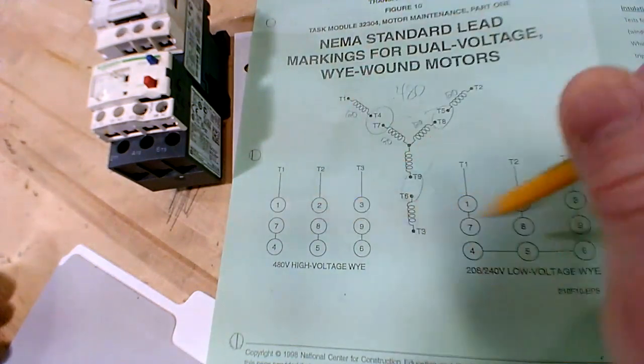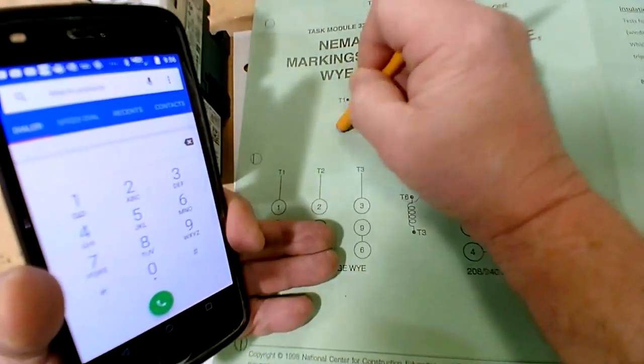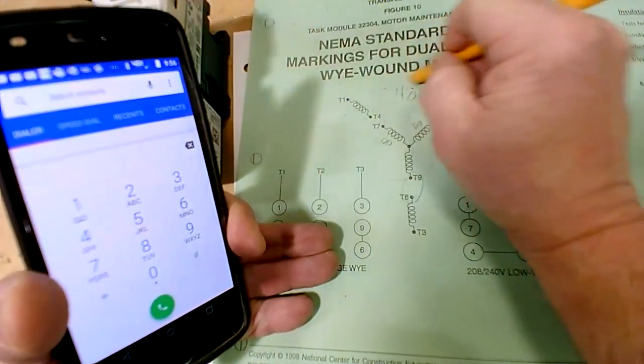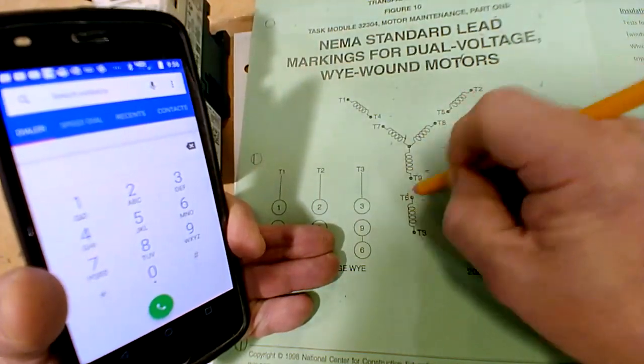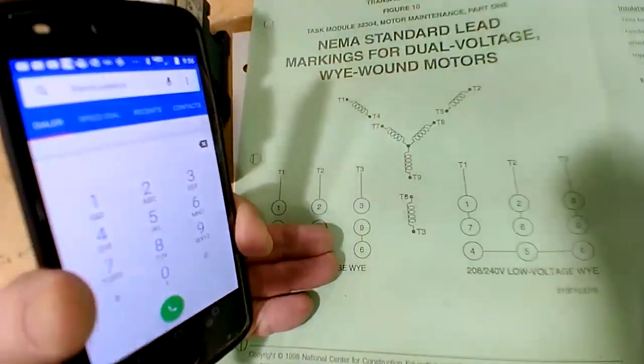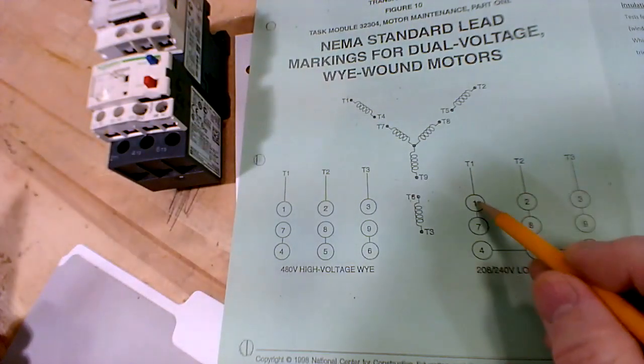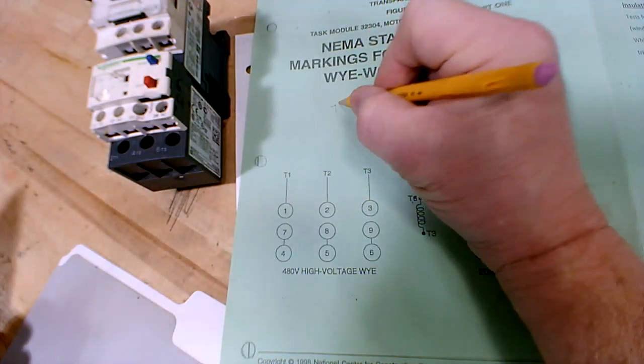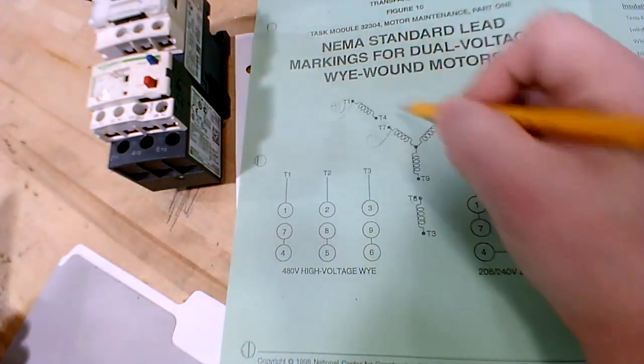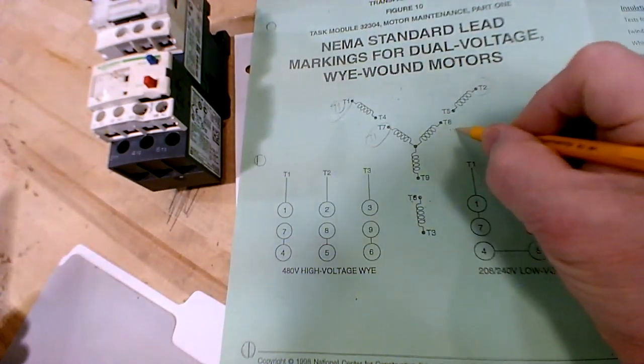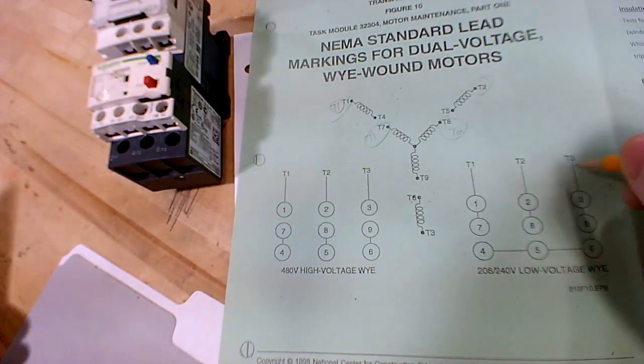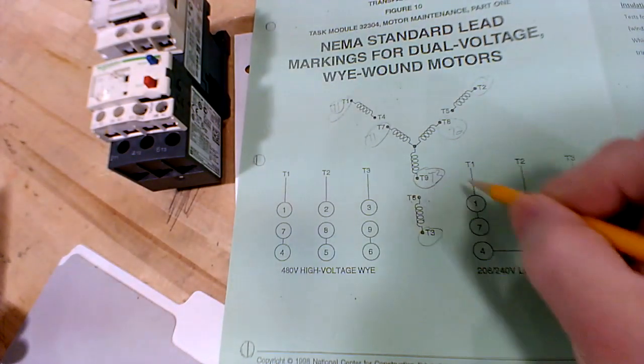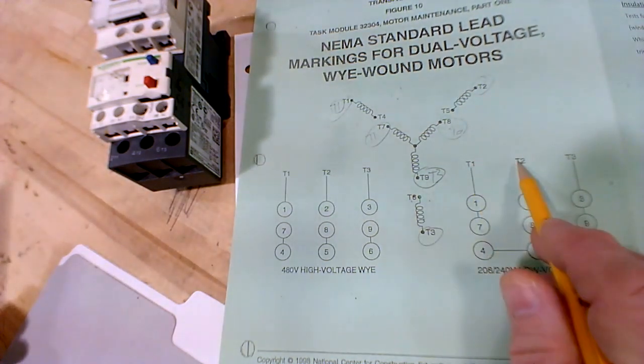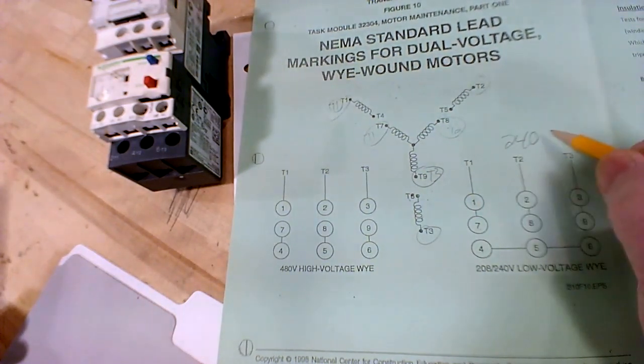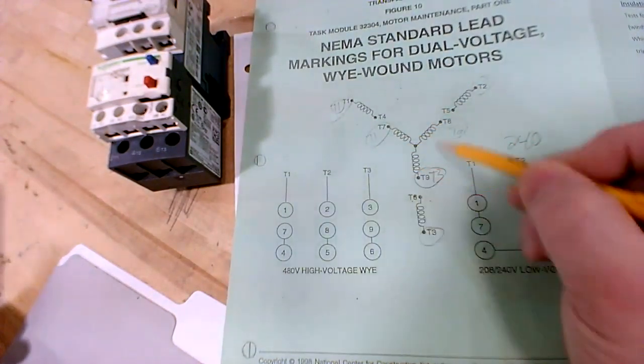But what happens when you go parallel? Let's just back that up. Let's erase this. Let's go parallel now. Get low voltage and find out, do the windings get the same voltage? So we go back to here, and now we have the 240 hooked up to 1 and 7, right? So we're going to say we've got T1 here, and we've got T1 here, right? And you've got T2 at 2 and 8. T2 here, and T2 is also right here, right? And then you've got T3 on 3 and 9. T3 here, you've also got T3 showing up here. So we know if we measure from 1 to 2, or 1 to 3, or 2 to 3, it's going to read 240, right?